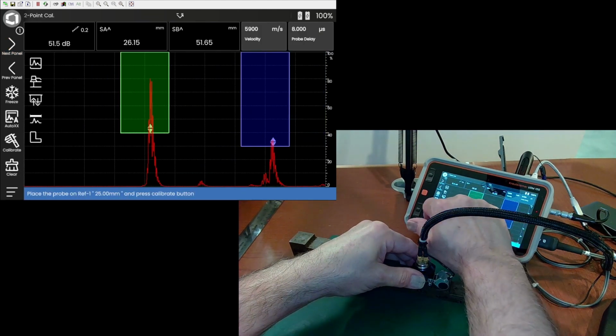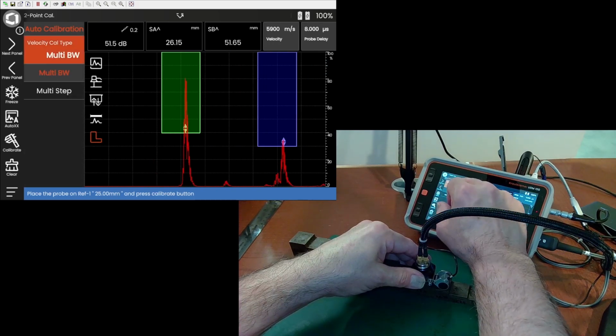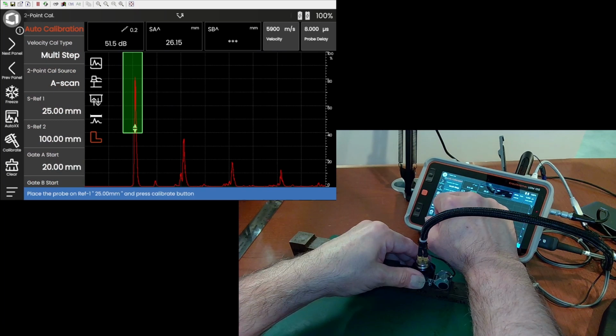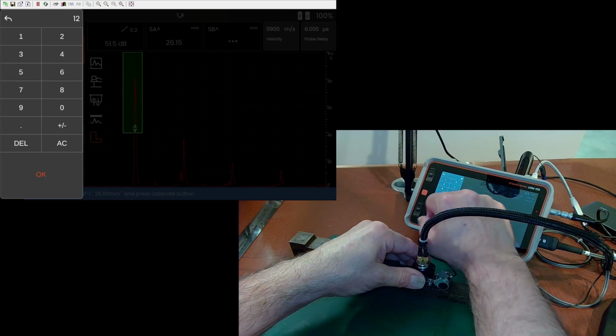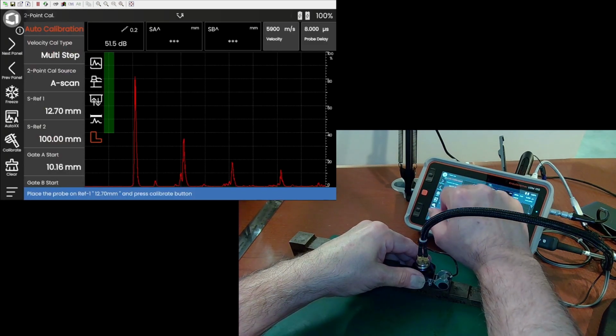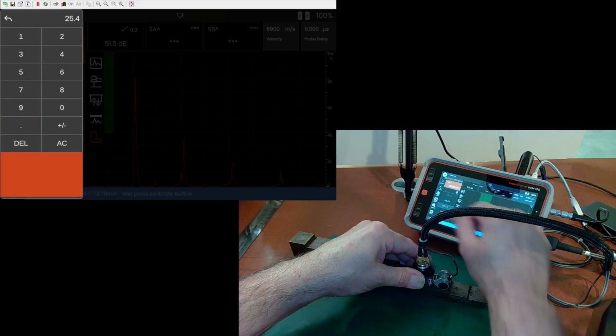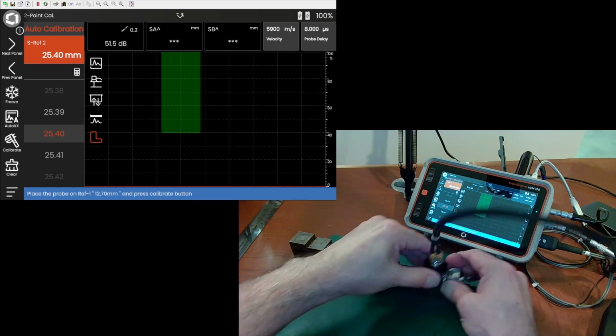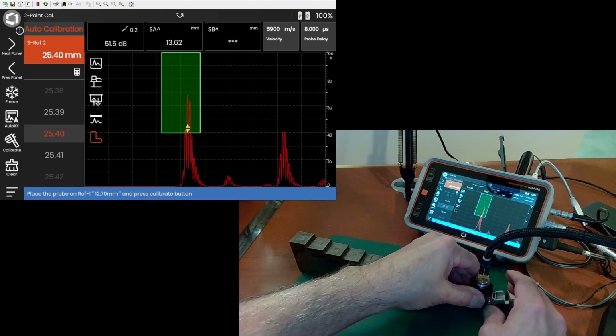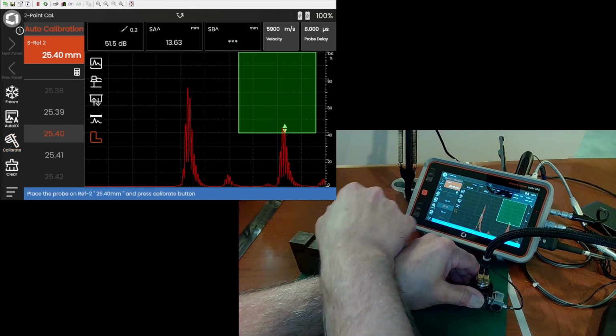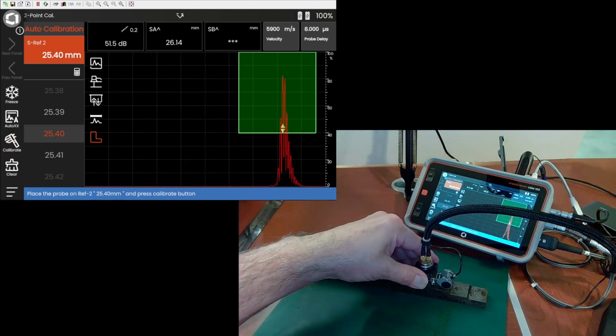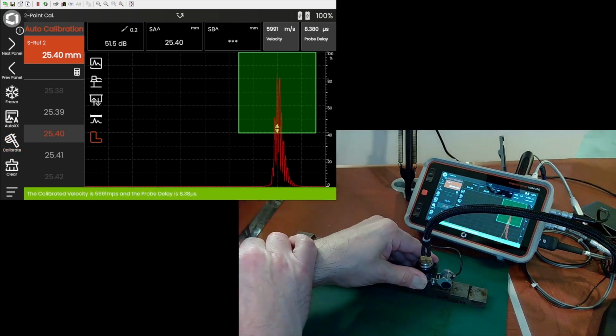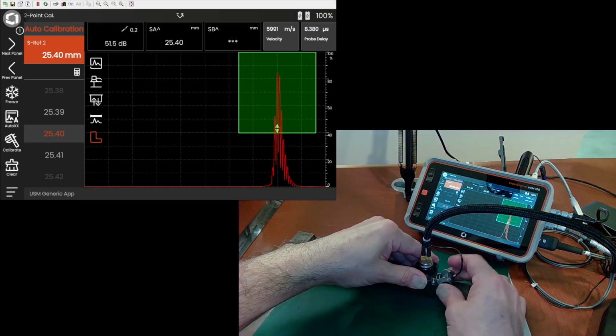And we'll go to our cal menu. We're going to do a multi-step calibration. We're going to go with 12.7 millimeters, a 1/2-inch step, and a 1-inch step. Okay, so let's go to our 1/2-inch step. Peak up, hit calibrate. Go to our 1-inch step, peak up, hit calibrate. And we have 5991 and 8.380.